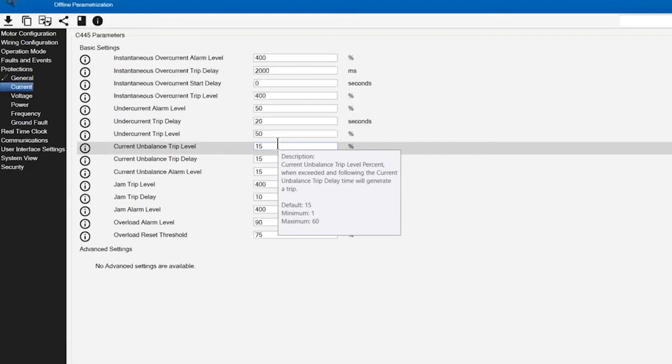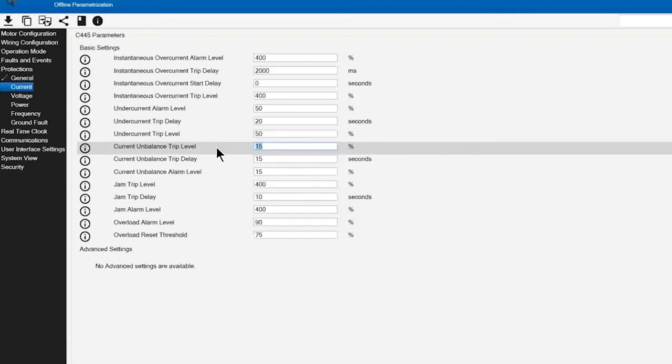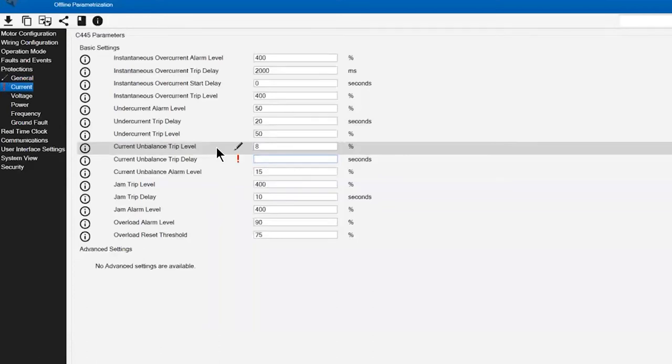This default setting of 15% in my experience is a little bit too lenient. The motor is typically going to be under pretty significant duress if we're at a point of 15% imbalance. I would generally gauge to reduce that down to an 8% value, which is what I'm going to do, as it's more in line with NEMA considerations on the design of that motor.